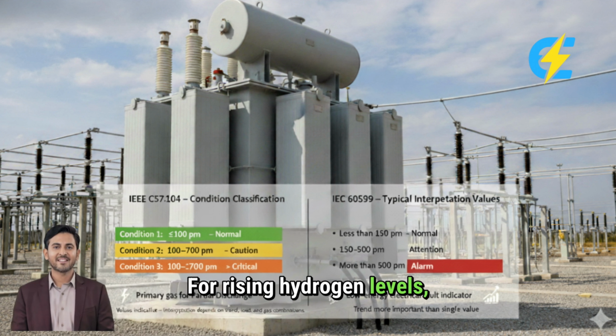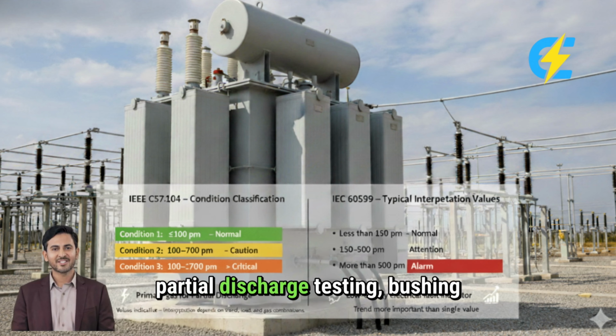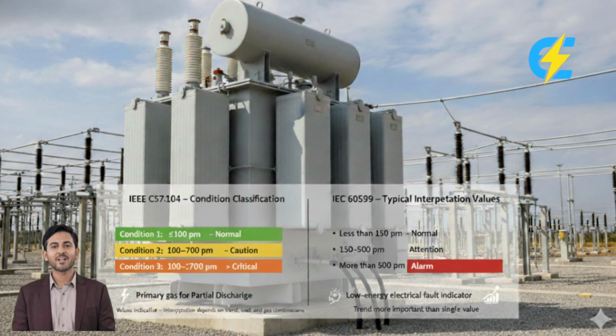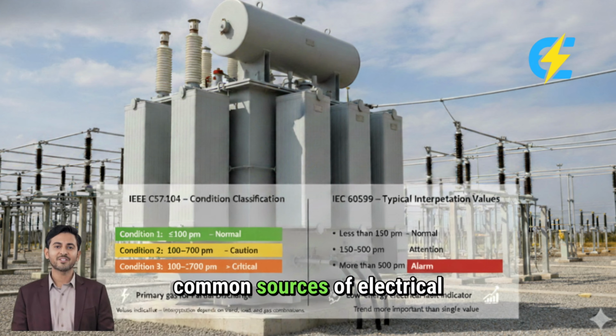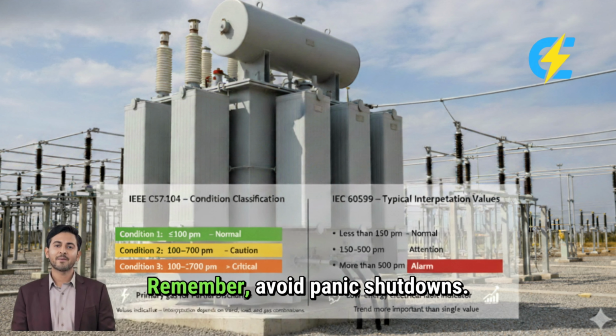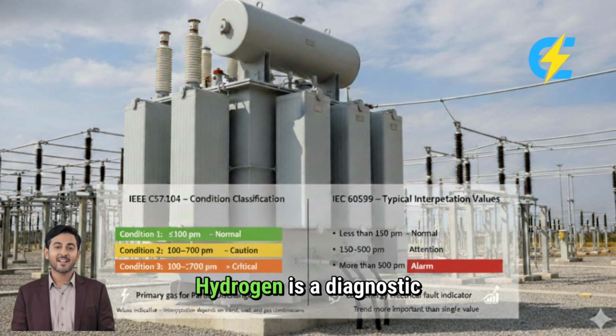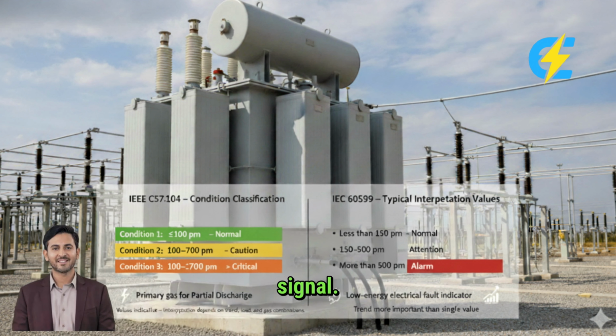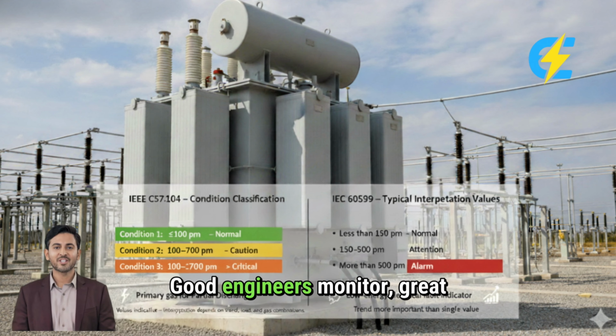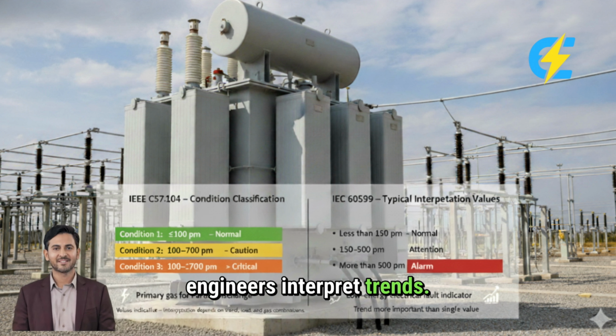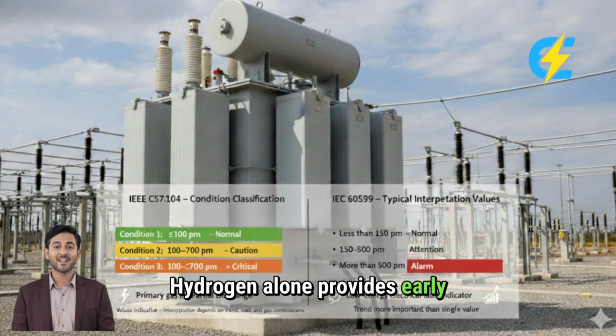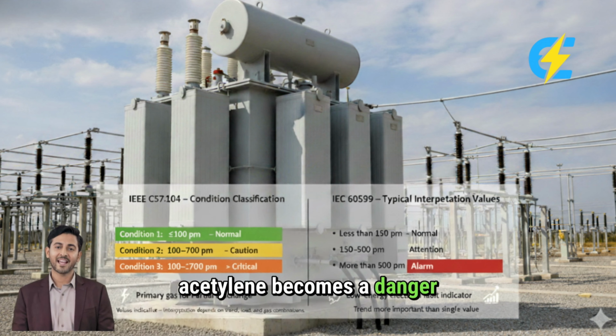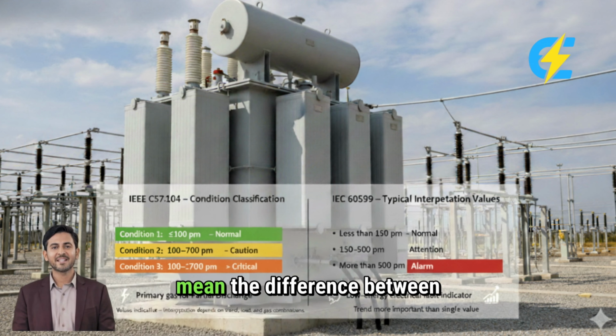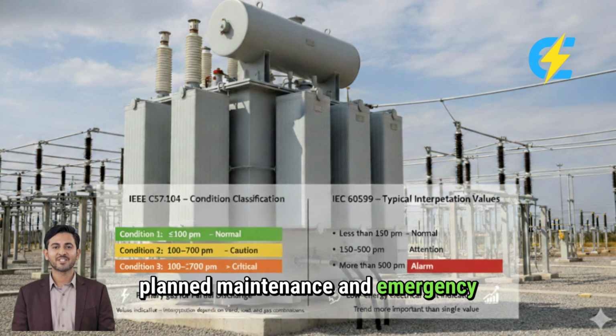For rising hydrogen levels, further investigation should include partial discharge testing, bushing condition review, and checking earthing systems. These are the most common sources of electrical stress that generate hydrogen. Remember, avoid panic shutdowns. Hydrogen is a diagnostic gas, not a trip signal. It's designed to give you time to investigate and plan corrective action. Good engineers monitor, great engineers interpret trends. DGA is not about one gas. It's about patterns. Hydrogen alone provides early warning, but hydrogen with acetylene becomes a danger signal. Understanding this distinction can mean the difference between planned maintenance and emergency outages.